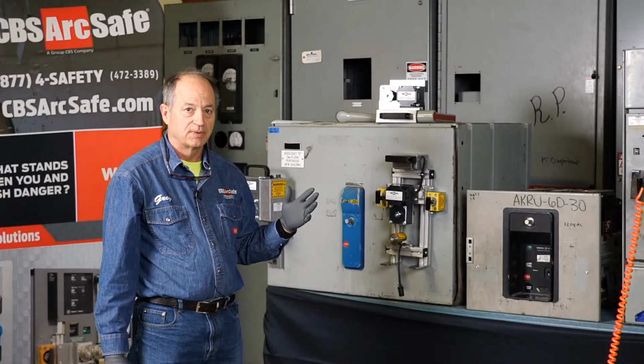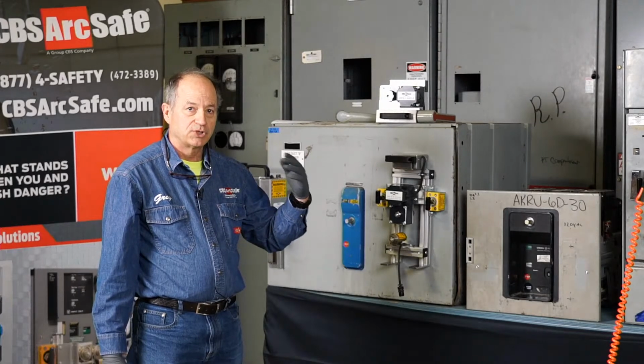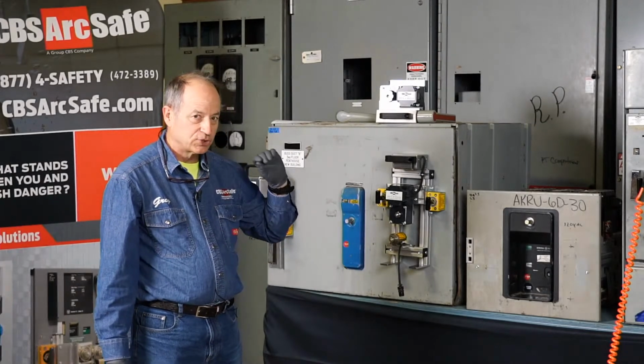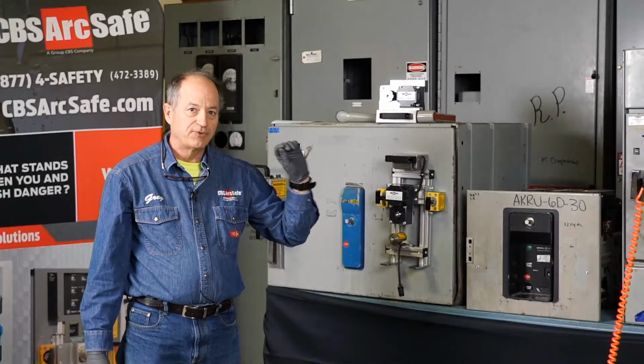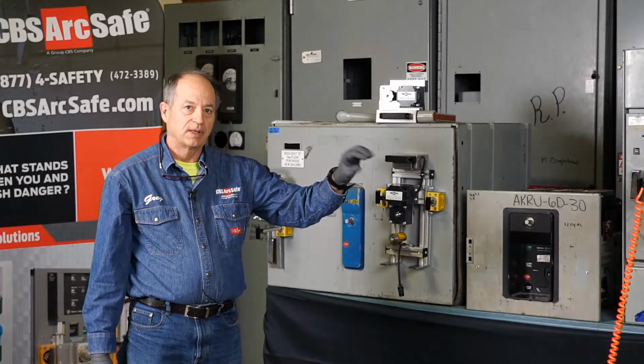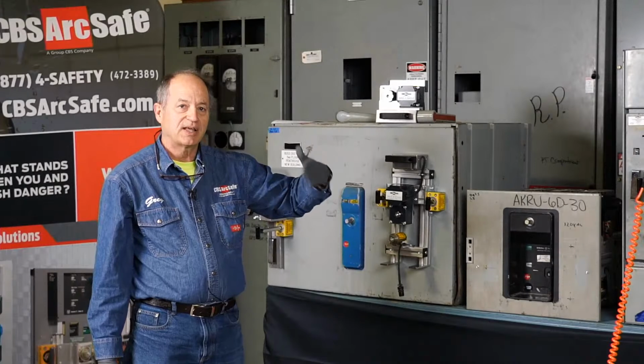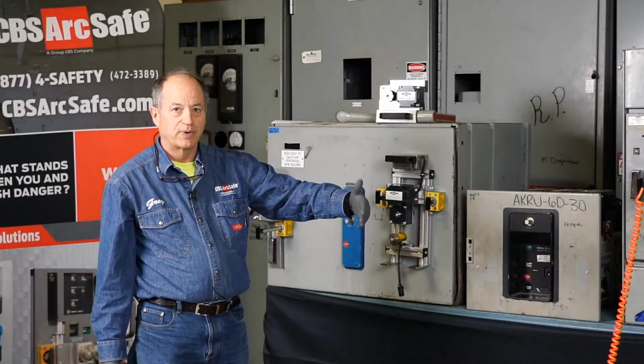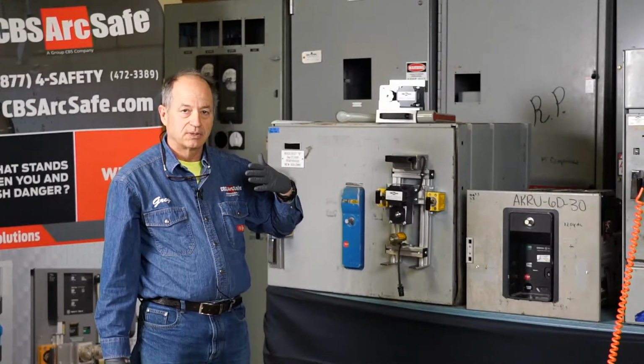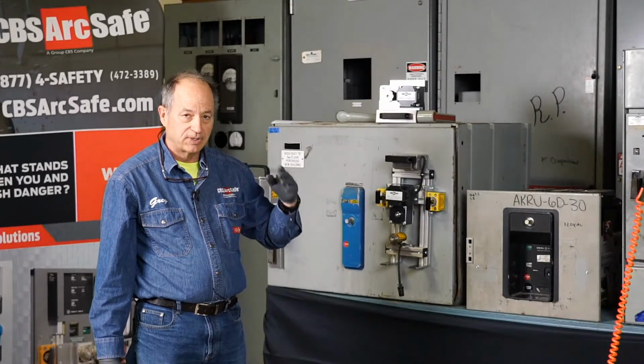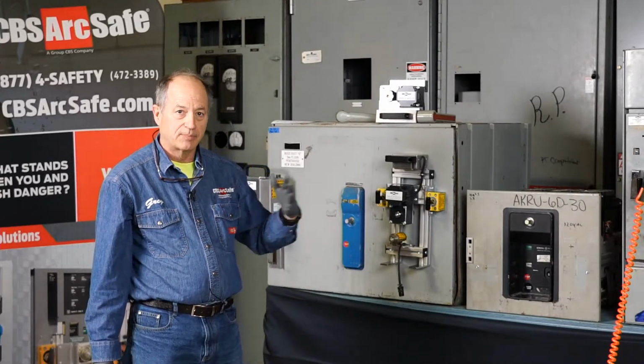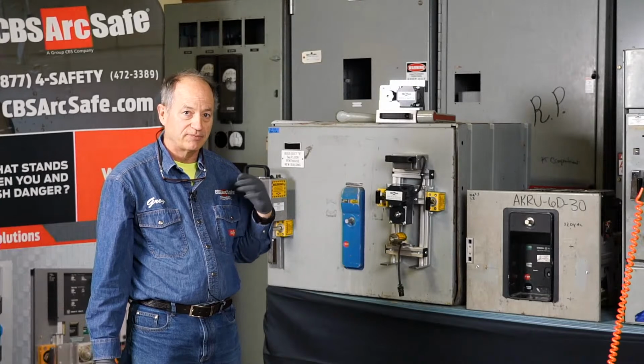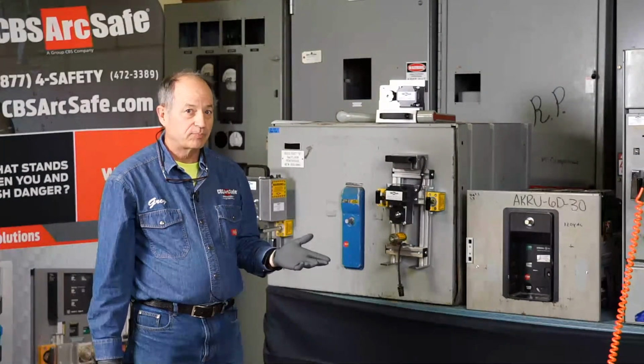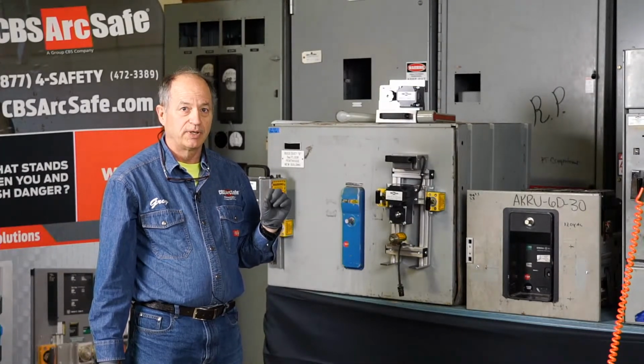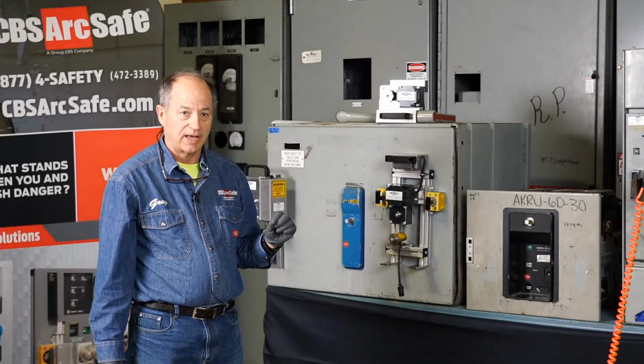So these are things that we know and can show you. The peak force should always be when the finger clusters spread. If you're seeing something different from that, other than when you get to the end of the screw going on and off the bus, if you see something different than at the end of the racking operation where it takes more to get a breaker off than to go on the bus, you have a problem and need to be willing to address the maintenance issues you have.